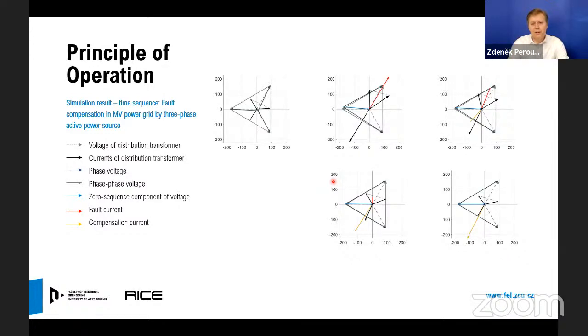How the current source operates. The first figure, which you see here, is the operation of the grid without the ground fault. When the fault occurs, we can observe an immediate rise of the fault current, which has, as I said at the beginning, two components, the capacitive one and the active one. And our current source starts immediately to compensate the fault current, producing the compensation current having the same magnitude and opposite phase. You can see how the compensation current rises and acts against the red fault current. And finally, we are able by our current source to fully compensate the fault current in the system. So that's the idea how the system works, and this is the simulation result.